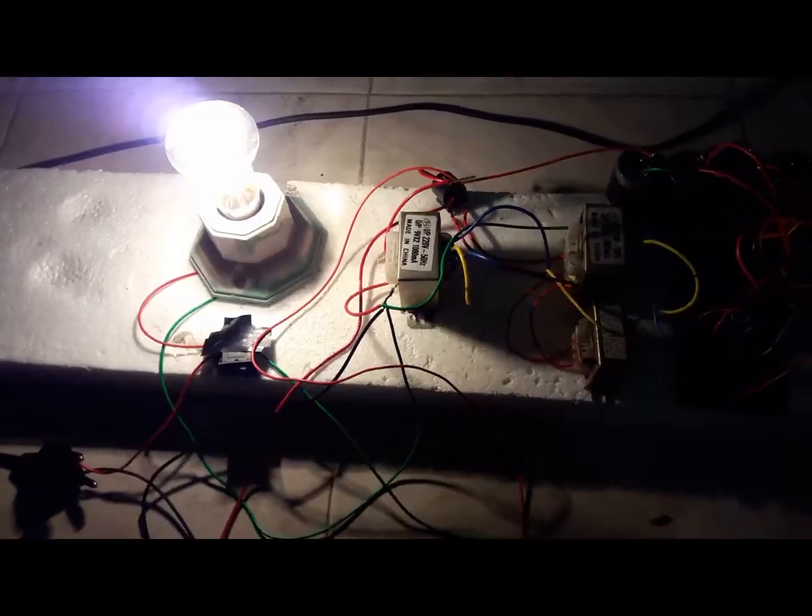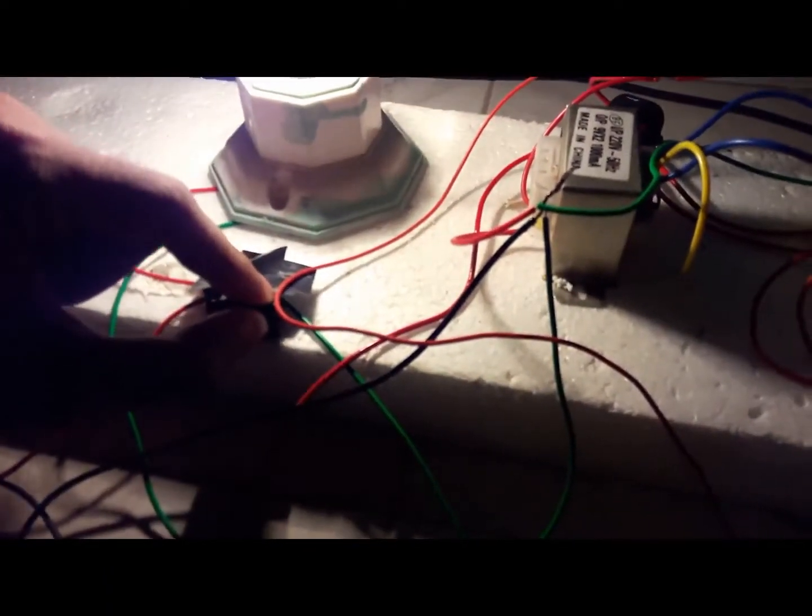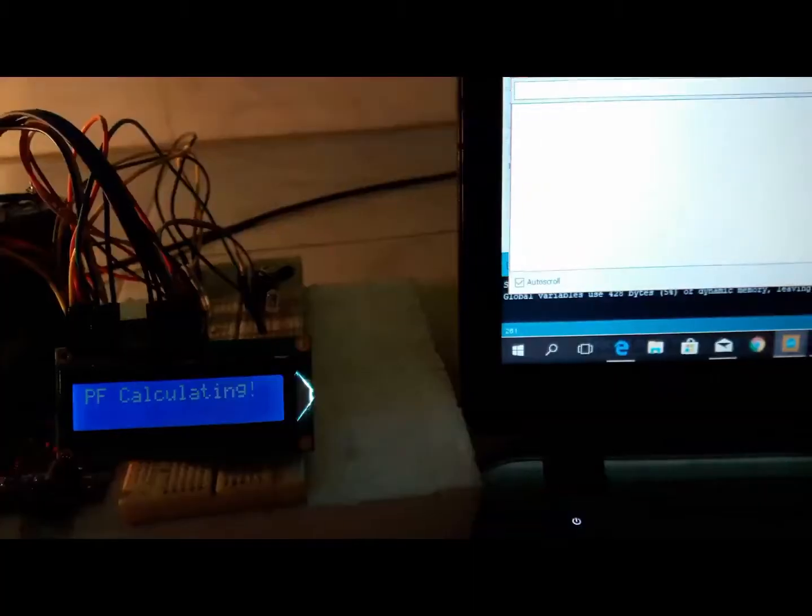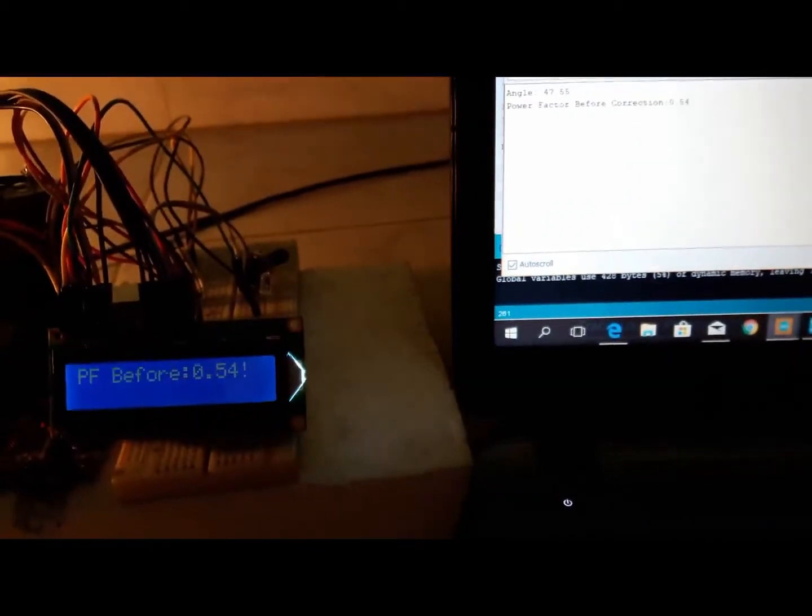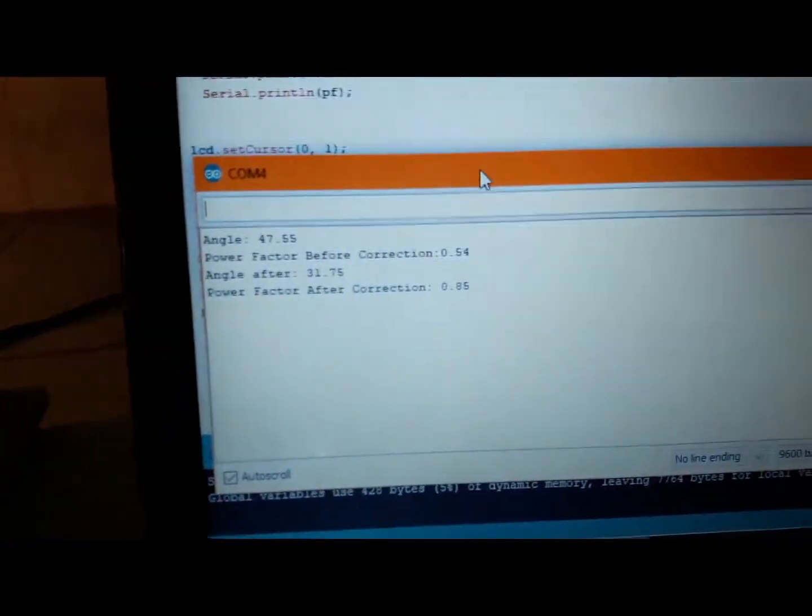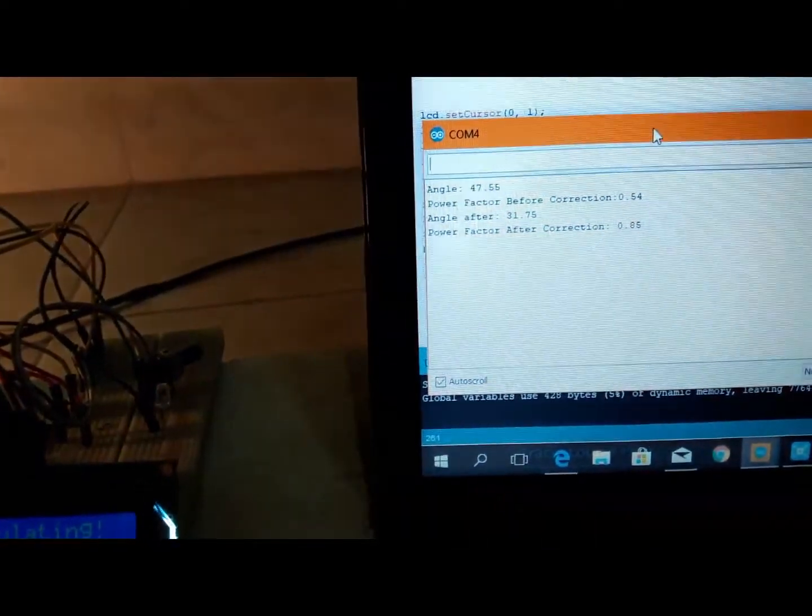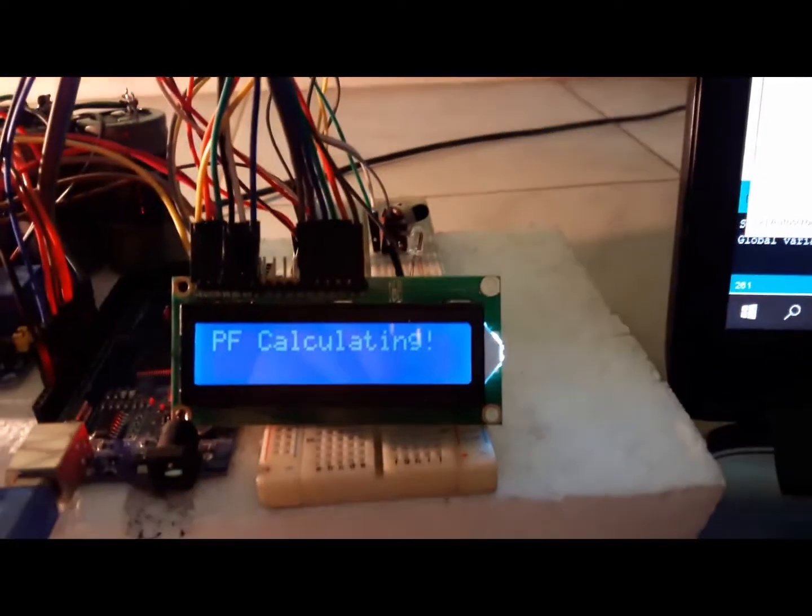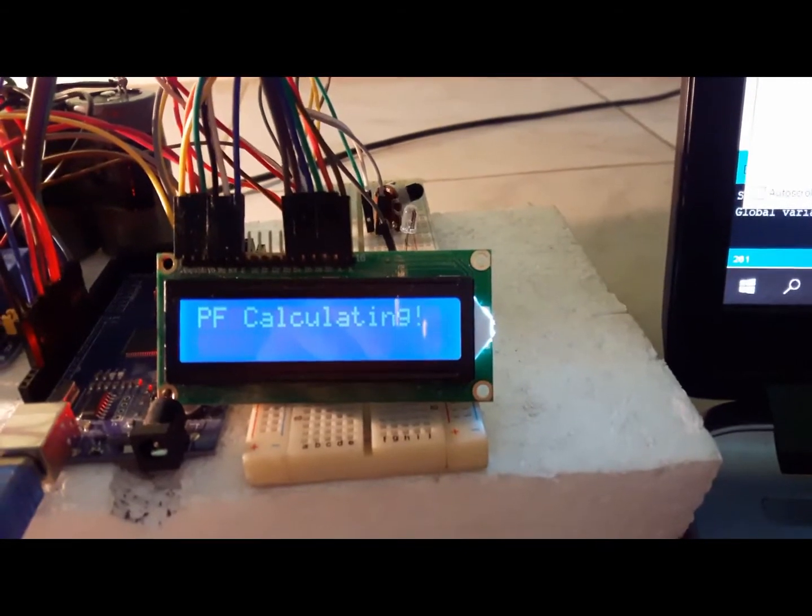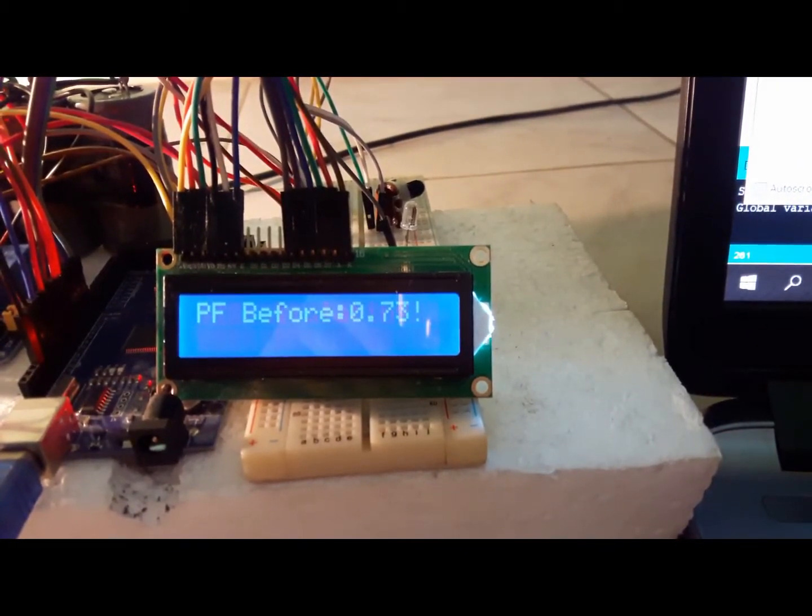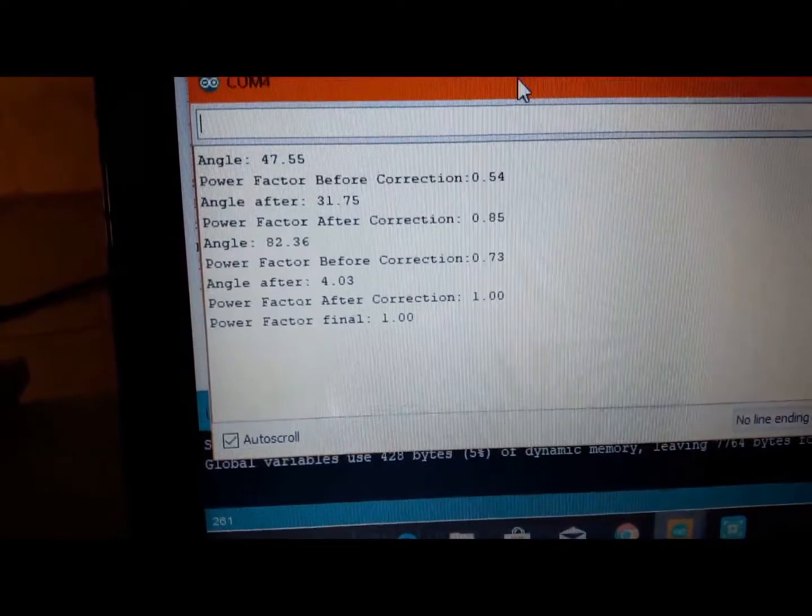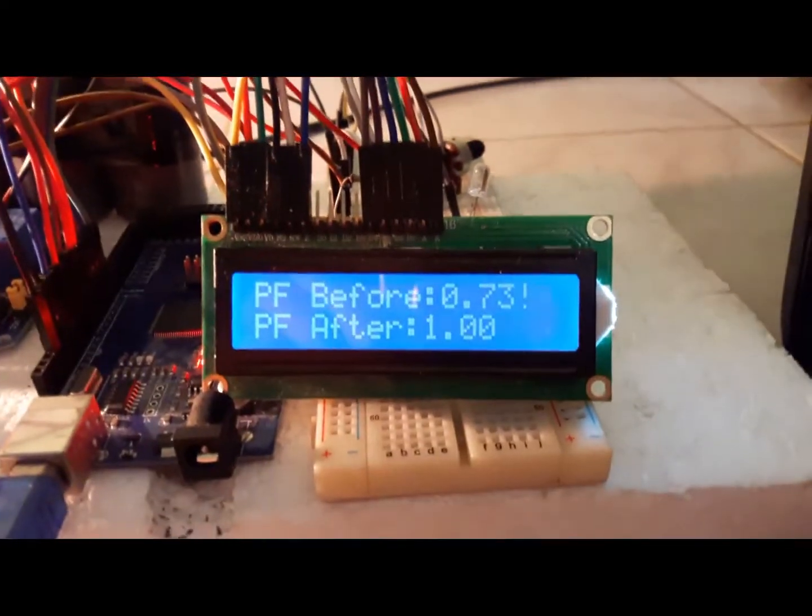Now we connect inductive load to test. Here we use inductive load as a fan in series with the incandescent bulb. First we see that power factor is 0.54 because it is inductive load. We use an iterative process. For second time it is 0.73. Now for third time we can see our expected value, PF 1.